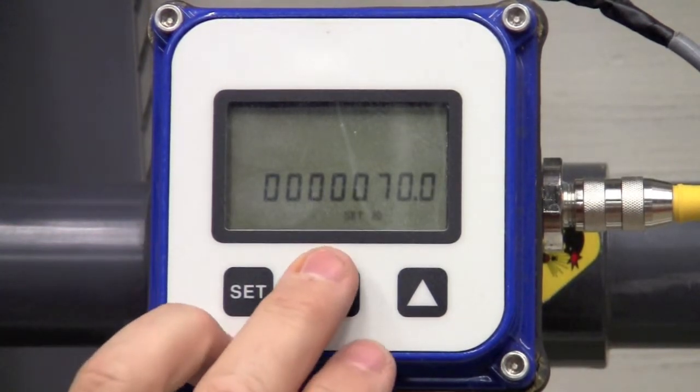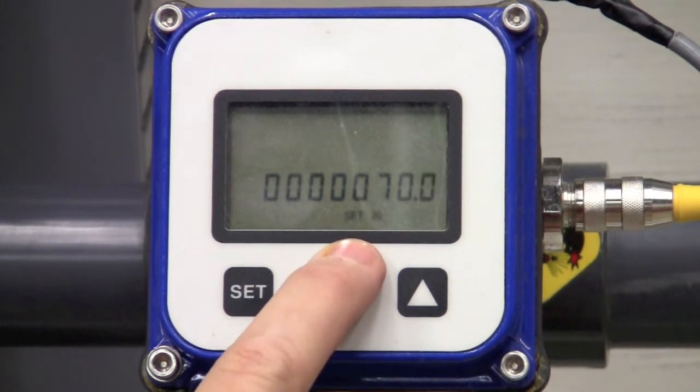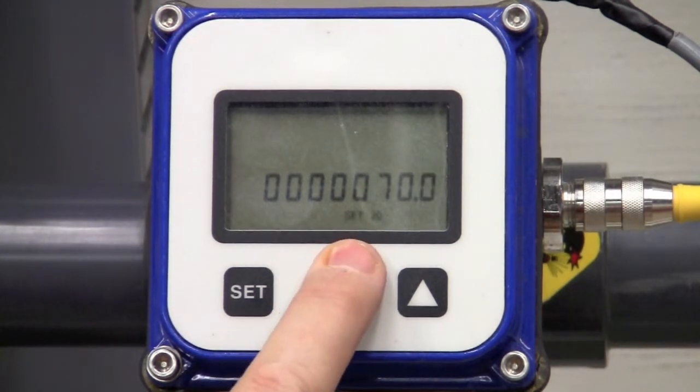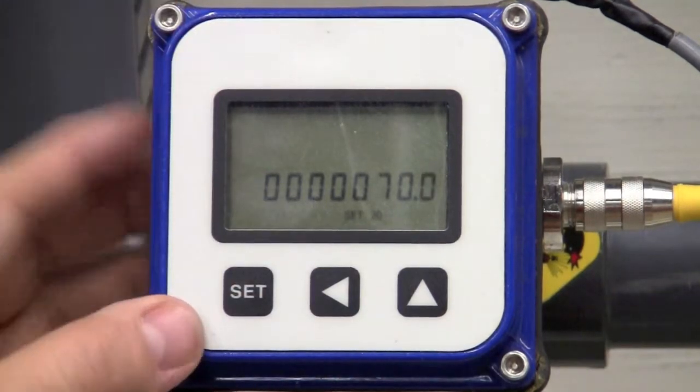The next parameter you put in is your 20 milliamps or your span. This will be the output to a PLC, or DCS, or chart recorder, or whatever you're doing with a 4 to 20 milliamp signal. Typically, 4 milliamps will output at zero, and what we're doing here is setting the 20 milliamp. Right now, I have it at 70 gallons per minute.